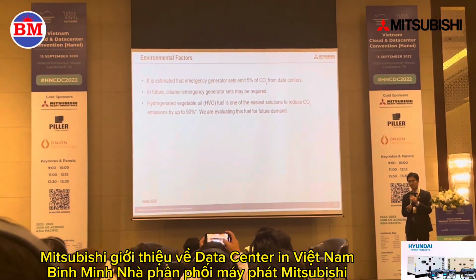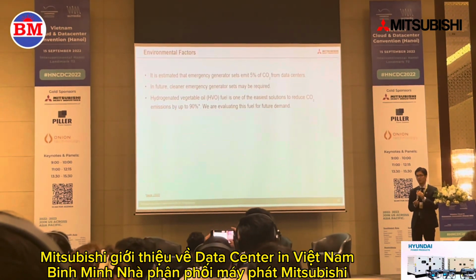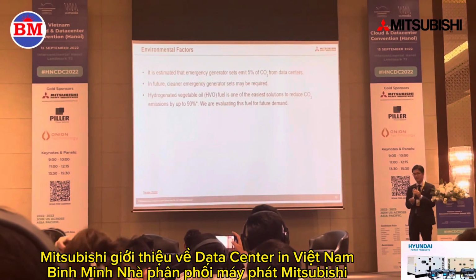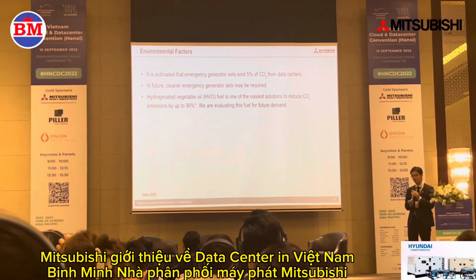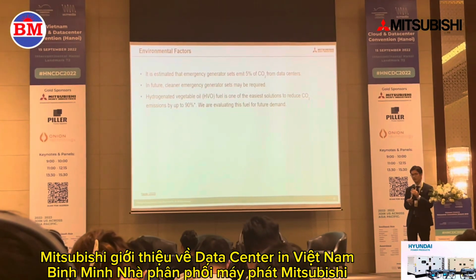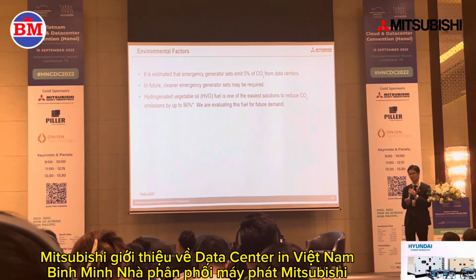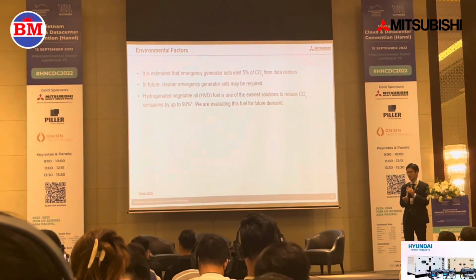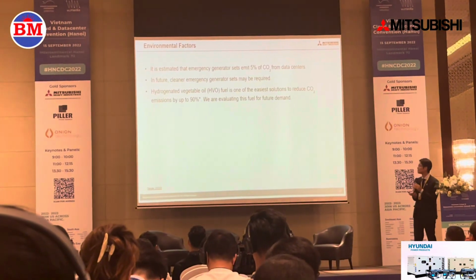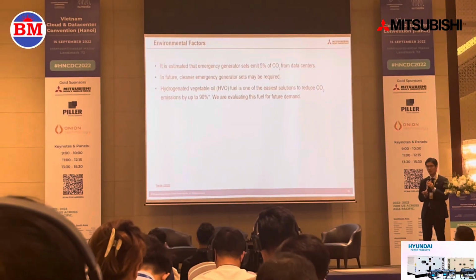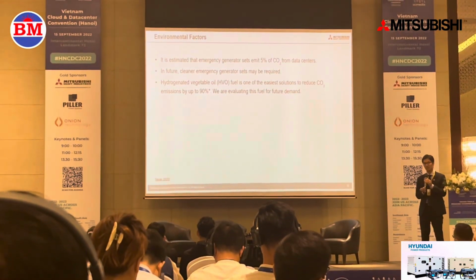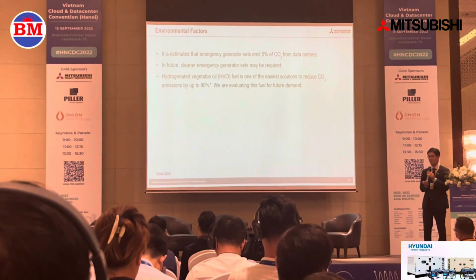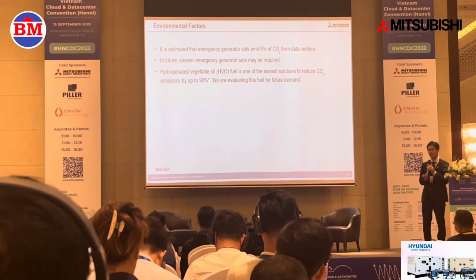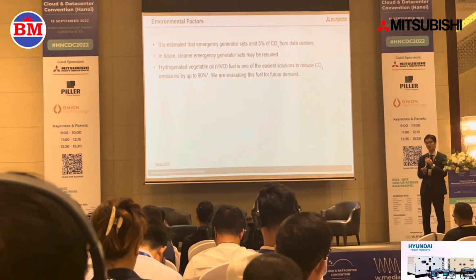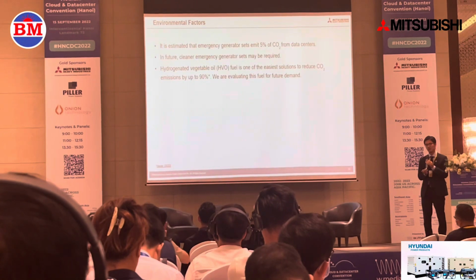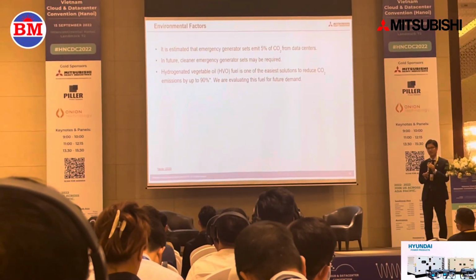Lastly, I'll touch on the environmental factor, which is becoming very important now. It's said that emergency backup generators emit around 5% of CO2 for all data centers, which is not a small value. So customers require CO2 reduction for emergency power as well. To achieve this, changing the fuel is the easiest approach. Changing to a biofuel called HVO can reduce CO2 by 90%. We are also evaluating this fuel so you can reduce CO2 in diesel generator sets as well.